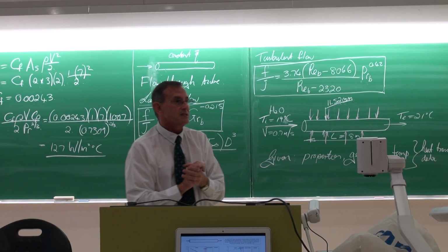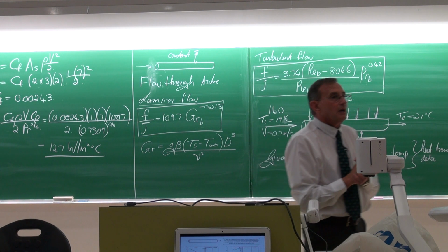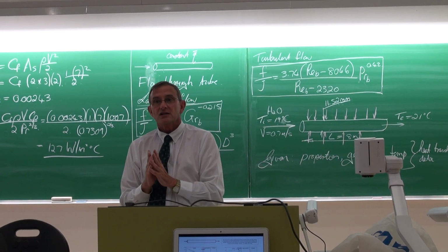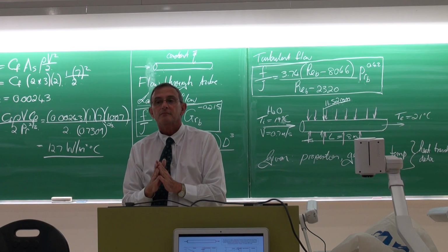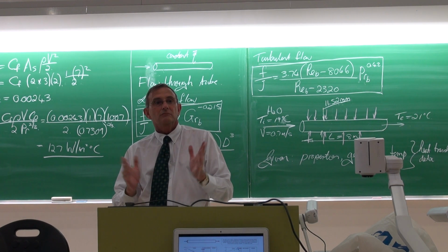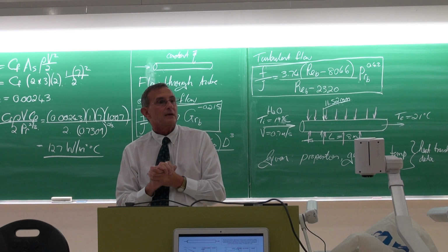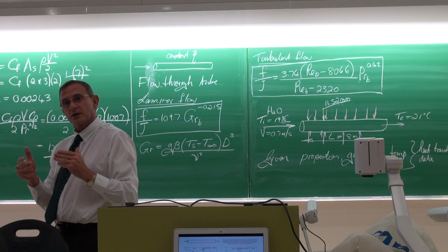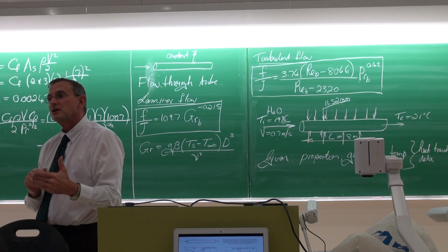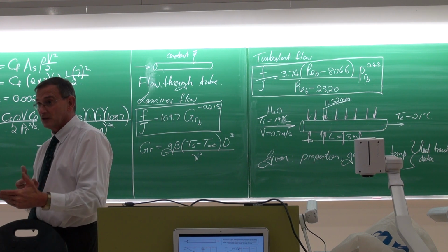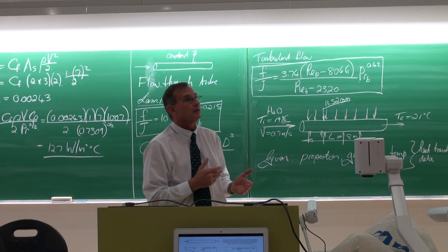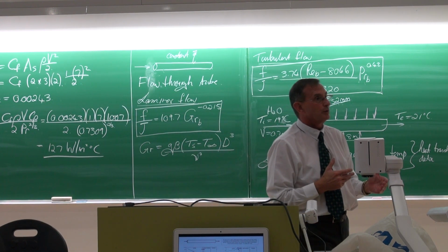The bottom line is, nature tells you, and unfortunately all the correlations are in many cases not available, but if you've got any heat exchanger, if you would, by pressure drop measurements, just go and determine what the pressure drop is, you should be able to calculate the heat transfer rate. Or if you know what the heat transfer is, you should be able to determine the pressure drop.